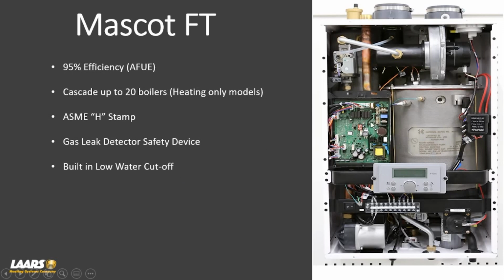We have a built-in low water cutoff. So right here on the heat exchanger, you'll see a red wire, and that is a built-in low water cutoff. A lot of inspectors want low water cutoffs out in the system. Again, state code will dictate that, but we have one built right in the cabinet in the top portion of the primary heat exchanger. That is an auto reset. So if somebody installs the boiler and didn't fill it or purge the air, your error code would appear on the display, but once you purge the air out of it, it automatically resets. It's not a manual reset.